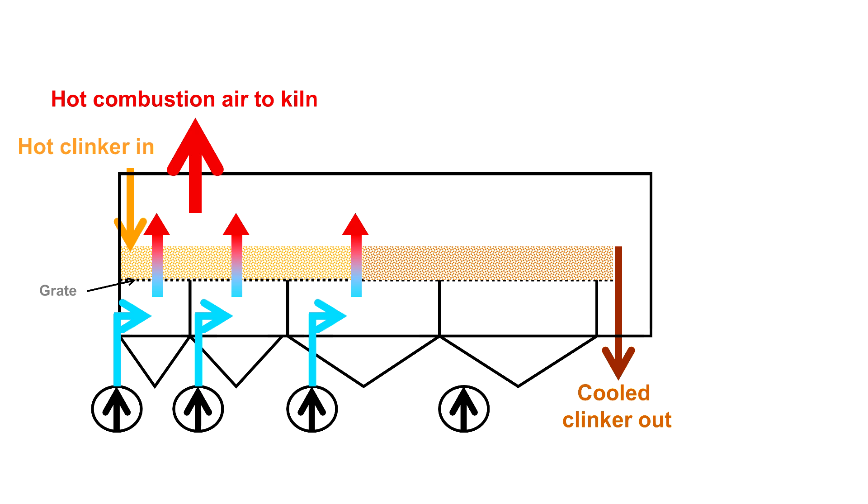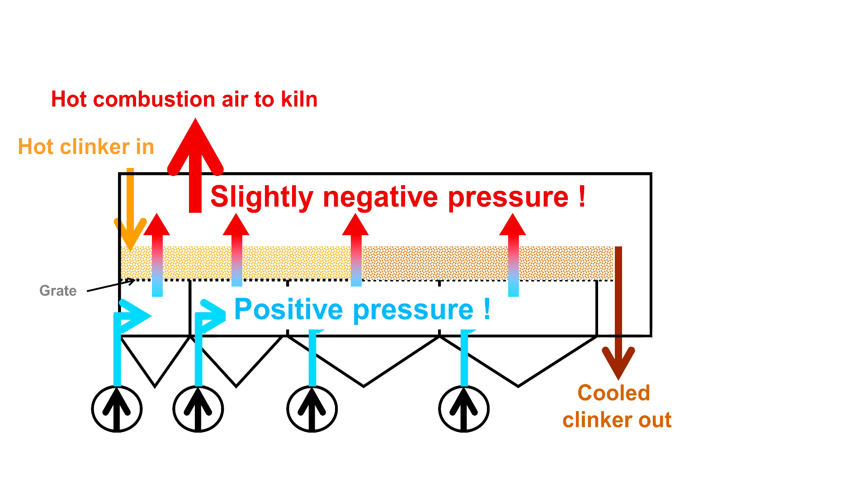We need a lot of air to cool down all this clinker. This air will create a positive pressure under the grate, but we want to keep a slightly negative pressure on top of the grate. For this, we need an additional extraction, so-called waste air.